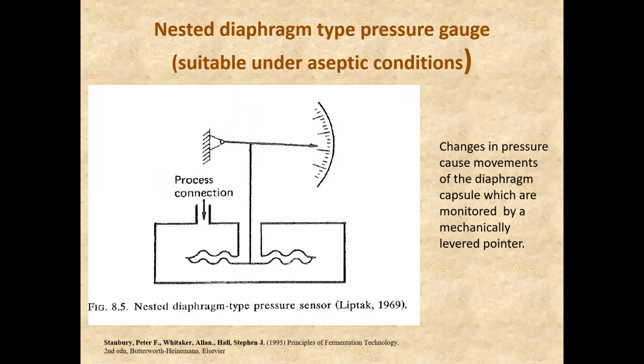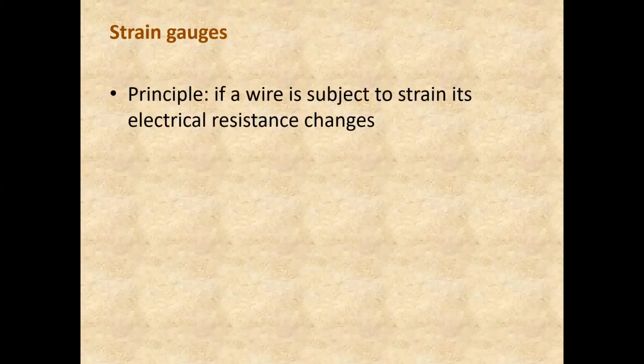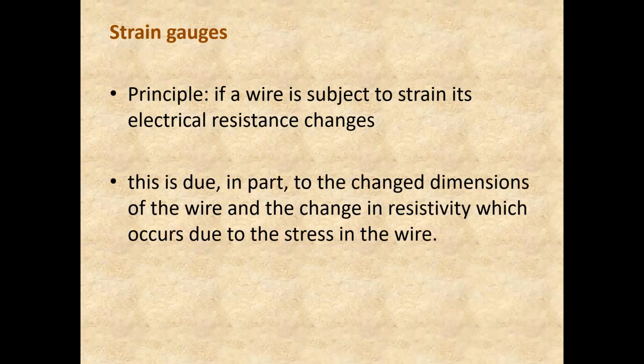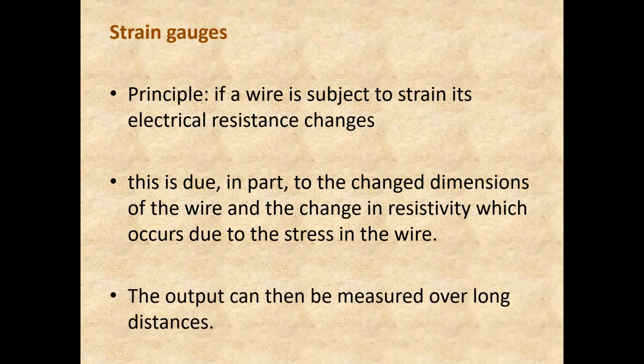After this diaphragm gauge, we'll study the third type of sensor, which is strain gauges. It's possible to use pressure sensors incorporating strain gauges. What is the principle? If a wire is subjected to strain, its electrical resistance changes. Now, why does the electrical resistance change when a wire is subjected to strain? This is due in part to the changed dimensions of the wire and the change in resistivity which occurs due to the stress in the wire. The output can then be measured over long distances. So this was all about strain gauges.